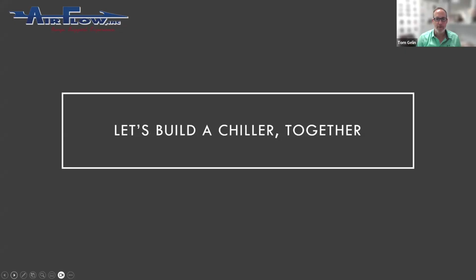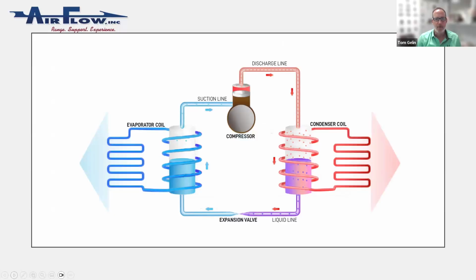And we're going to put the parts of a chiller together here. So once upon a time, I did just air-cooled heat pumps as part of a presentation. Boy, it sure is the same thing, less the reversing valve. So it looks different when it's in the chiller configuration, but this is all there is to it. Condenser, evaporator, expansion valve, compressor. And then there's some other parts that go on top of that, but that's the primary function. So let's go to the next slide.